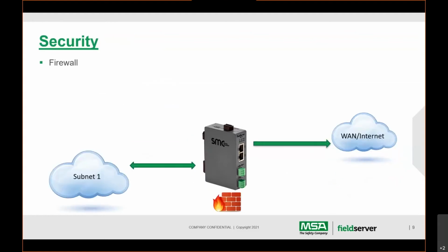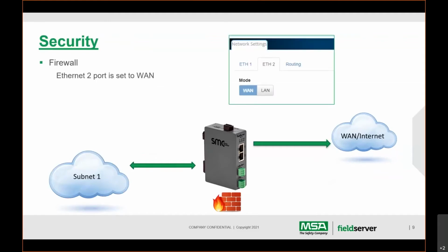So security. Let's go into more about the LAN-WAN connectivity. When you go into the configuration and you're setting up the second Ethernet port, Ether 2, you have the ability to go to LAN mode, or it comes standard with LAN, or you can switch it into WAN mode. In LAN mode, it's just normal protocol translation, connecting one network to another network, fine. But in WAN mode, it only allows an outgoing connection. So from the field server bridge, if you want to connect to the cloud, it will allow that. Everything else is firewalled. So if you want to come into Ethernet 2, you can't do it.